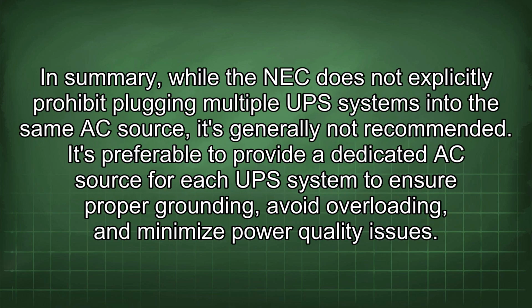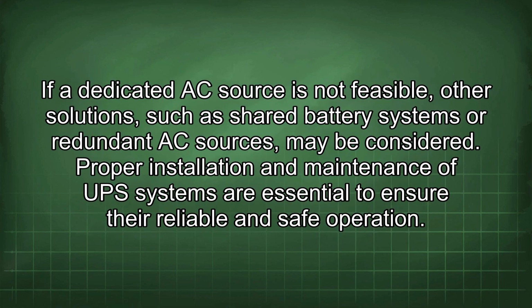In summary, while the NEC does not explicitly prohibit plugging multiple UPS systems into the same AC source, it's generally not recommended. It's preferable to provide a dedicated AC source for each UPS system to ensure proper grounding, avoid overloading, and minimize power quality issues. If a dedicated AC source is not feasible, other solutions, such as shared battery systems or redundant AC sources, may be considered. Proper installation and maintenance of UPS systems are essential to ensure their reliable and safe operation.